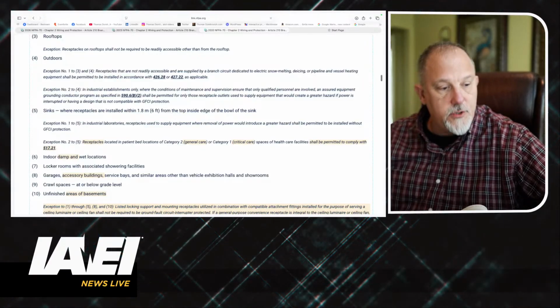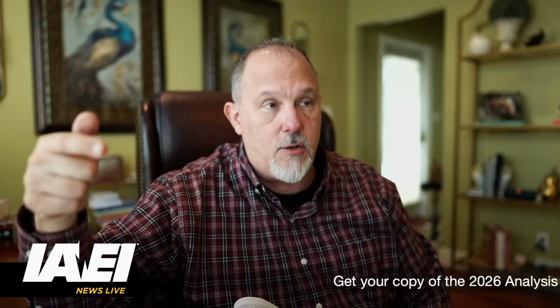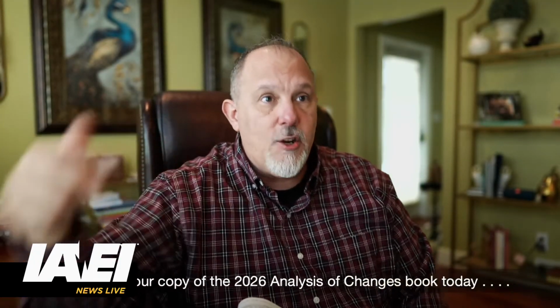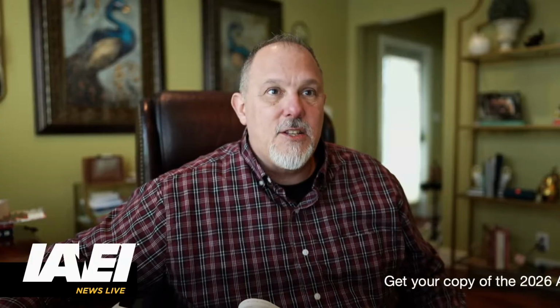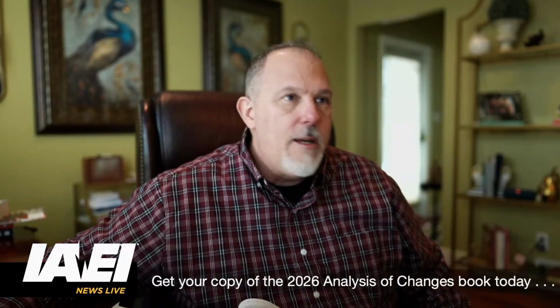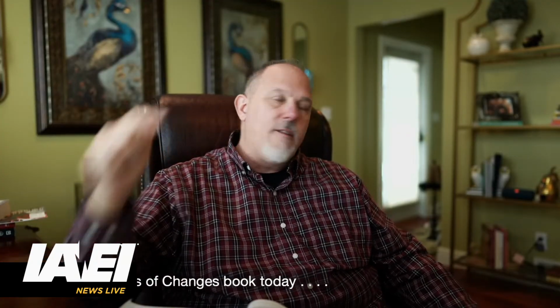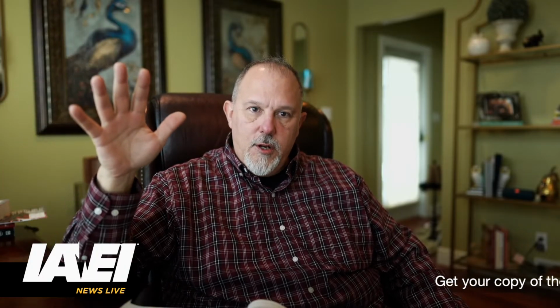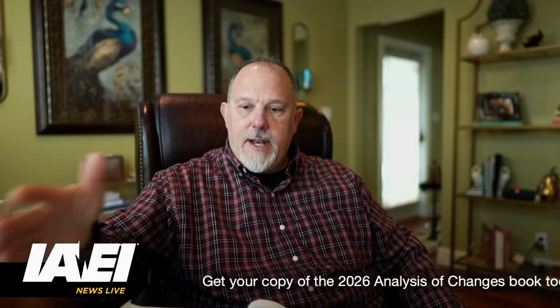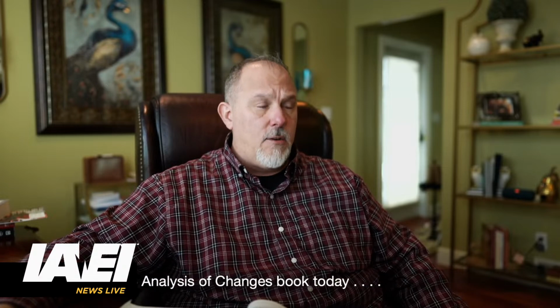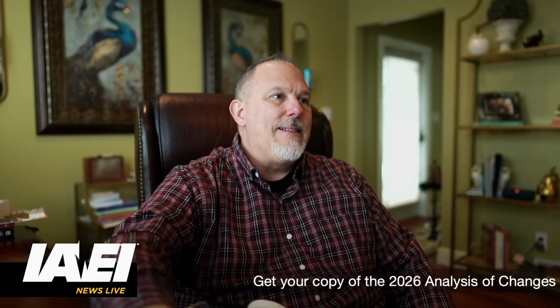Well, it's not all receptacles, right? It was only for those outside receptacles, and only when those receptacles supply equipment that would create a greater hazard if it lost power. Somehow, last cycle, we made it generic. No receptacle within the top inside edge of a sink within 6 feet. That was not our intent. That was never on the task group. I don't know how the heck that happened. I did not take the time to go through all of my notes on panel 2, but it happened. So what we did this cycle is we went back. We went back in time.